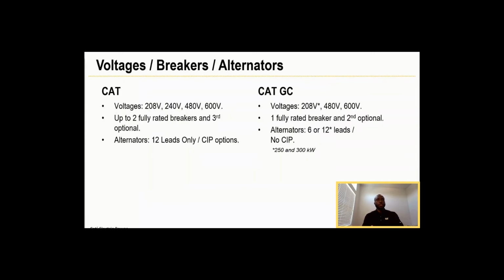Going into voltage, breakers, and alternators: for the CAT traditional product, we have 208, 240, 480, and 600 volt. For the CAT GC, we have 208, 480, and 600 volt for Canada. With the CAT traditional product, you can get up to two fully rated breakers with a third optional. For CAT GC, given the vast majority of opportunities we see in North America, one fully rated breaker is needed with a second optional.